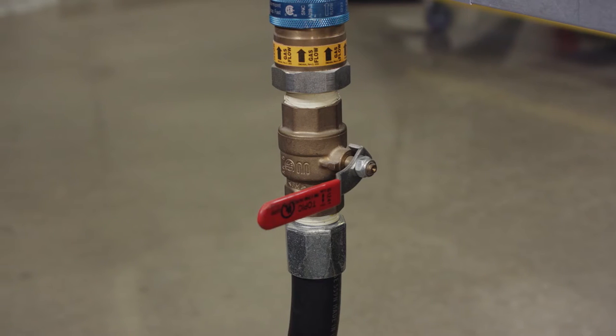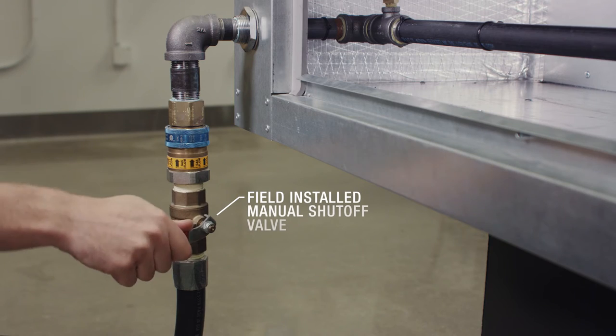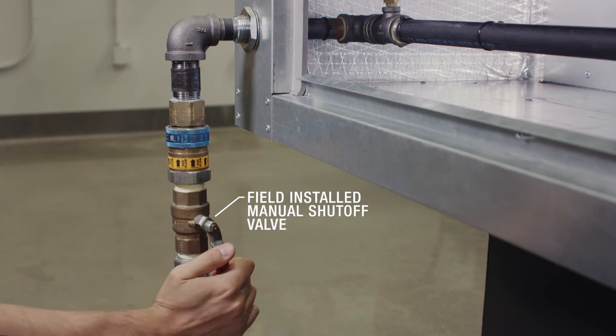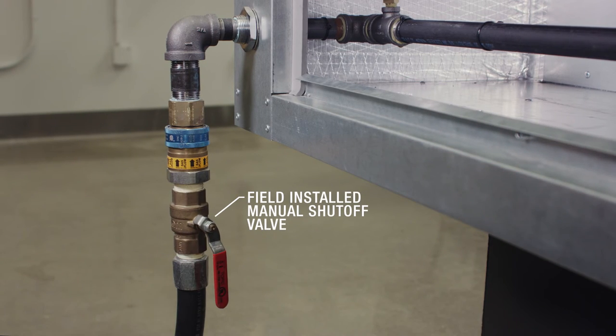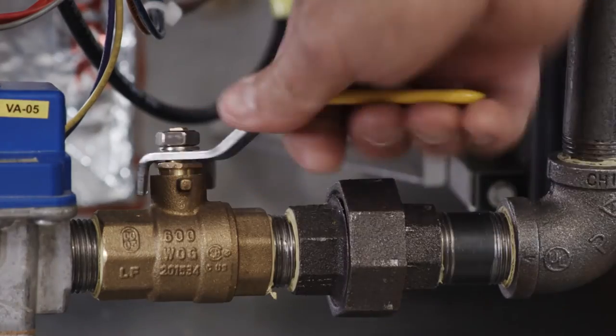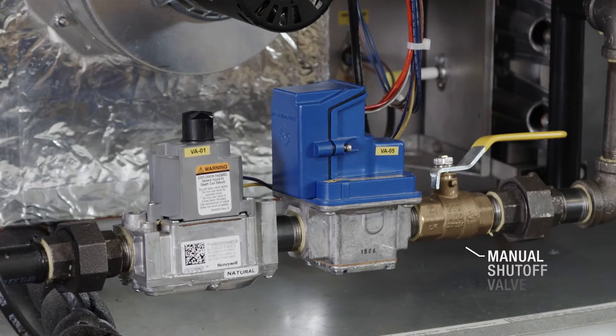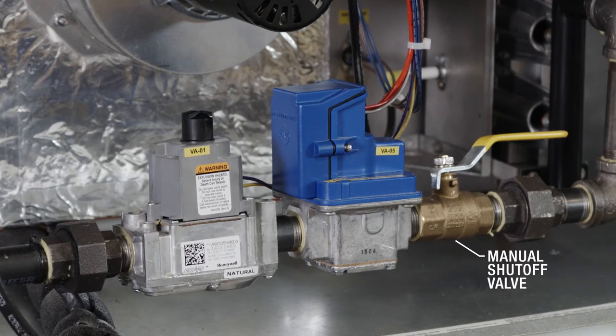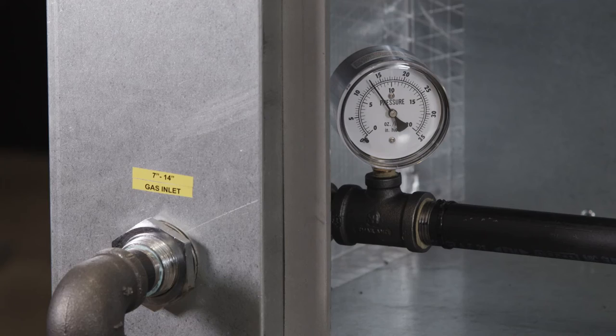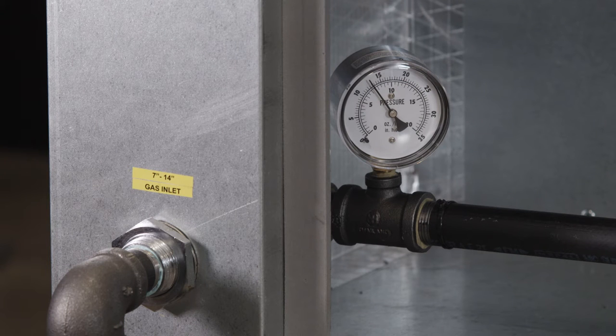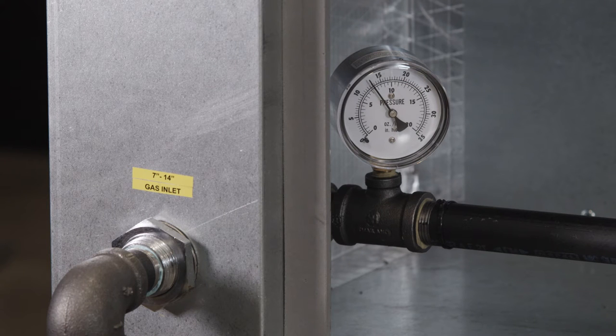Once pressure has been verified, open the field installed manual gas shutoff valve, as well as the manual valve on the gas manifold. Verify that the pressure on the gauge is between 7 and 14 inches water column.